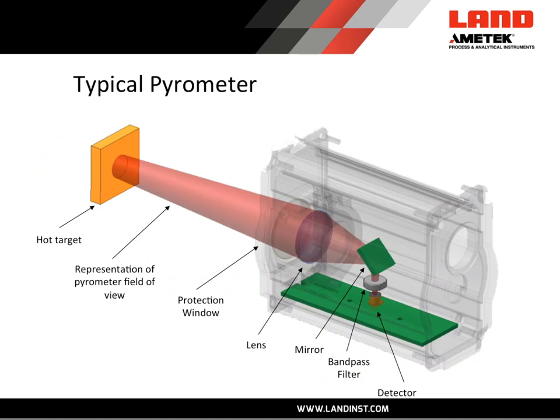Now let's look at a typical pyrometer and what goes into its design. Within the pyrometer body is a radiation detector. Usually in front of the detector is a bandpass filter which allows you to tune the response of that detector to certain wavelengths. In this particular design there is a front-faced mirror bending the ray cone towards the lens, a lens, a protection window, and a representation of the pyrometer's field of view going out into the distance and looking at a hot target.